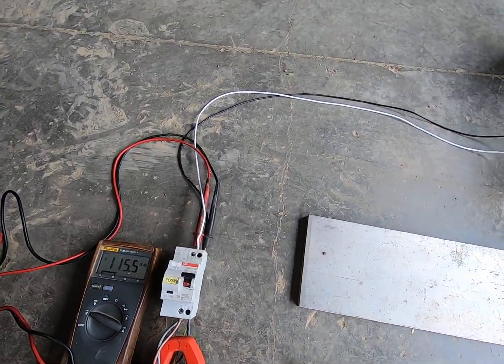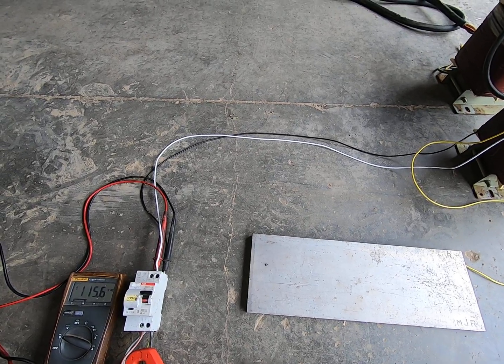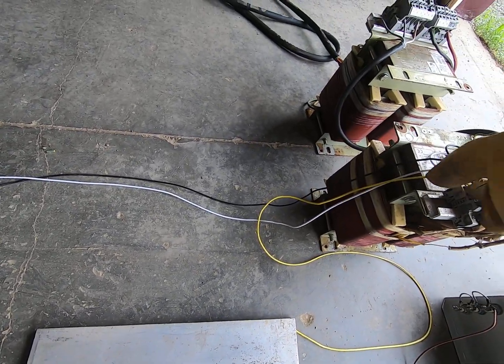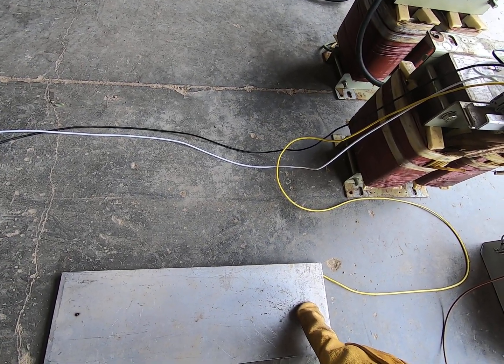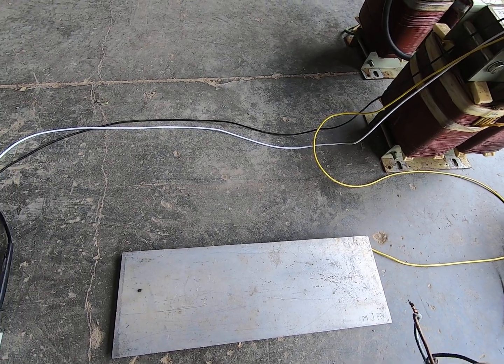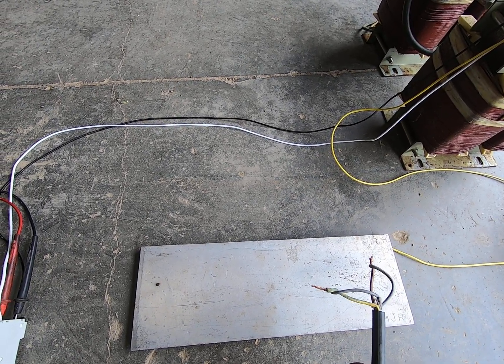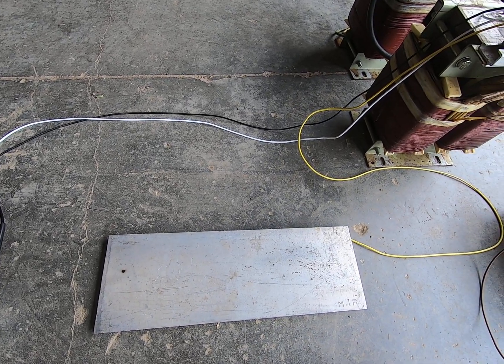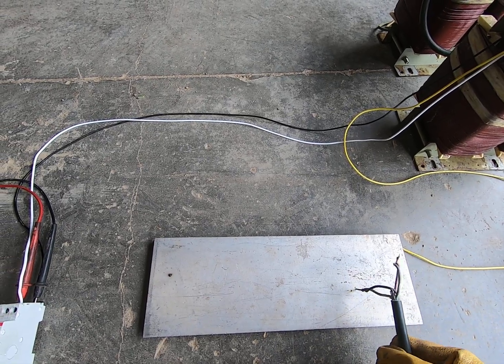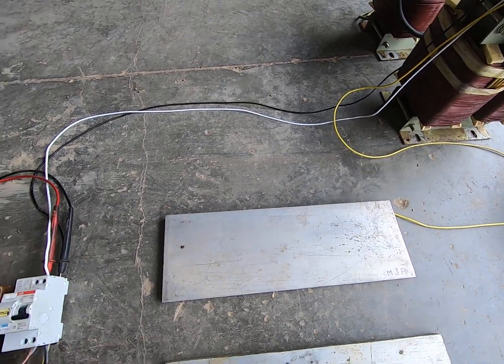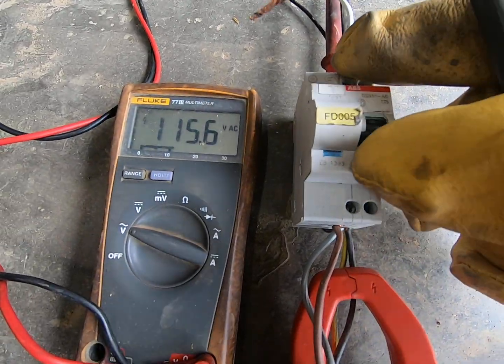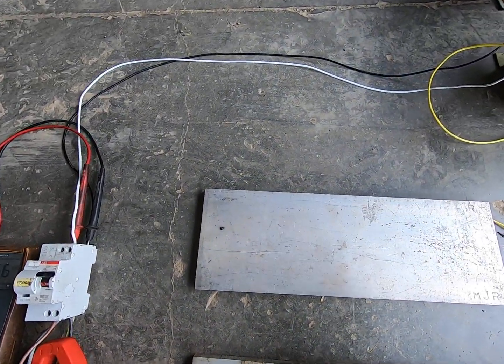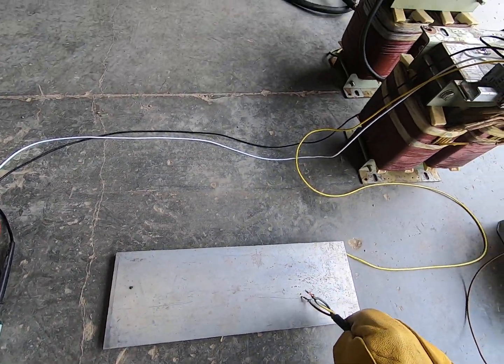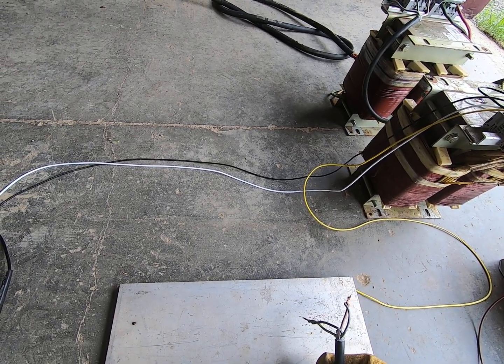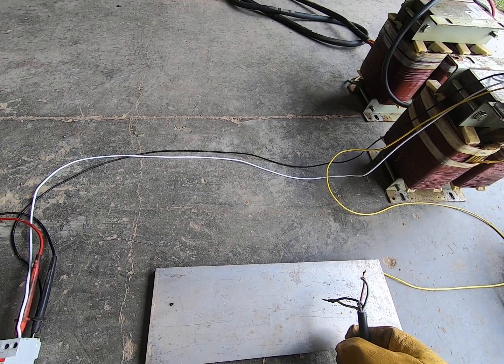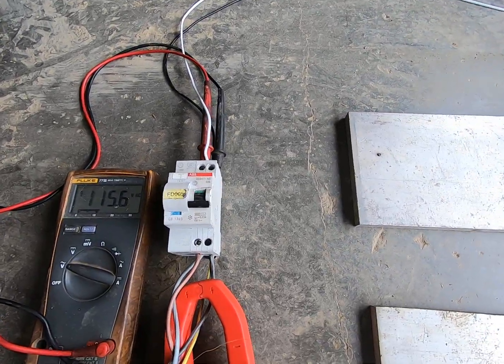The other test I can do is put an actual ground fault on the breaker. So as you can see, I have this yellow wire connected to this plate here, and then that yellow wire, if I were to short out the opposite of what's grounded on the transformer, so in this case, if I short out the ground, the green and black, the breaker trips, and you can see it trips on ground fault. Now if I short out the opposite wire, it's obviously grounded on the transformer side, so nothing happens. So again, I ground out the opposite wire, we get a little spark, breaker trips.